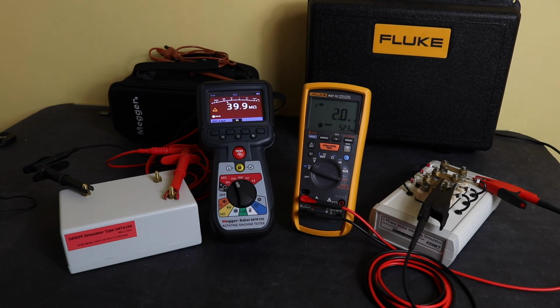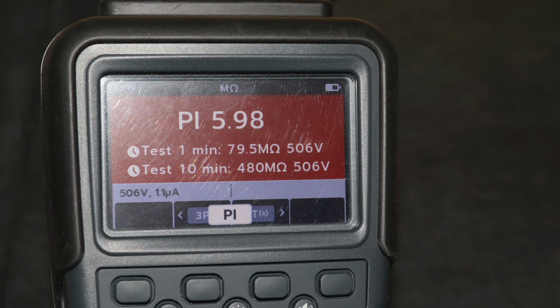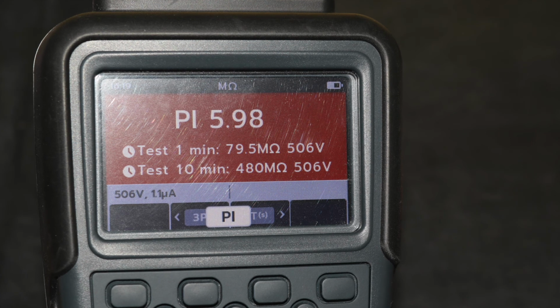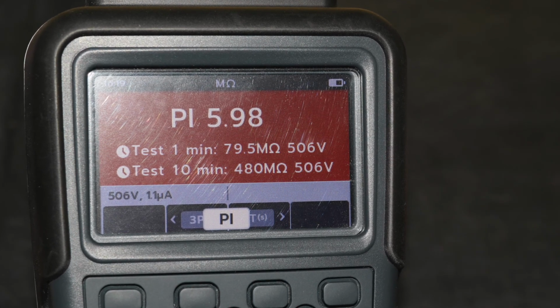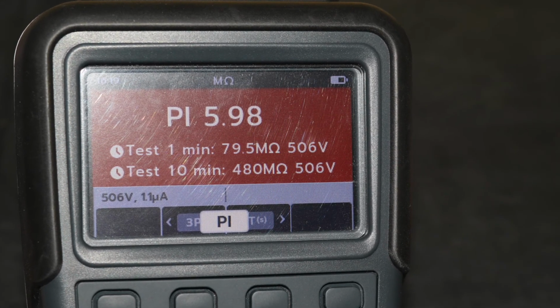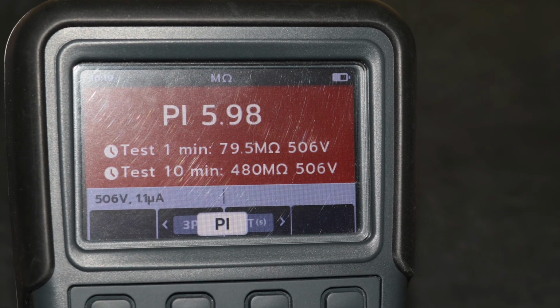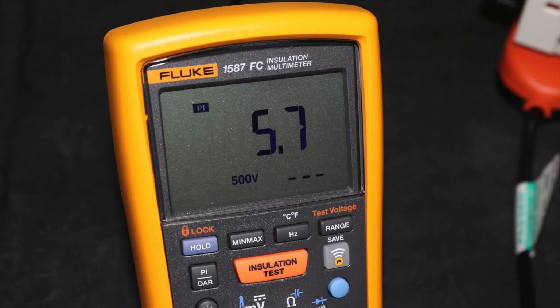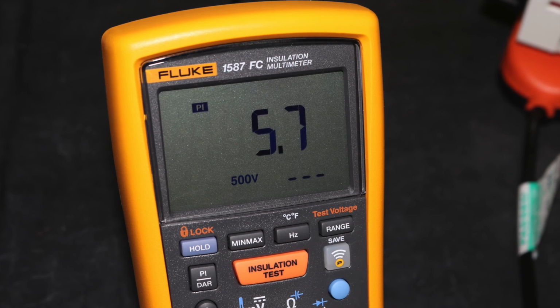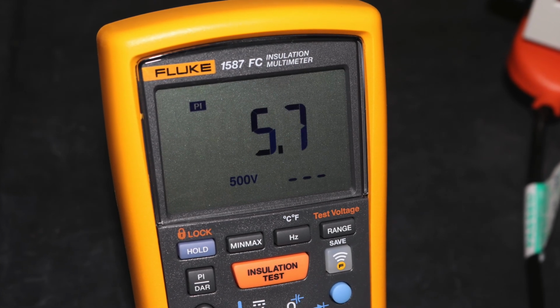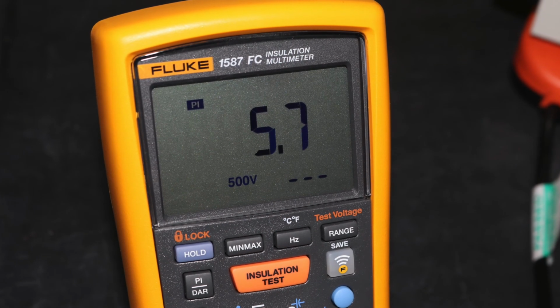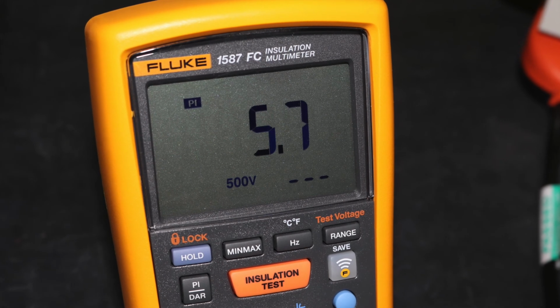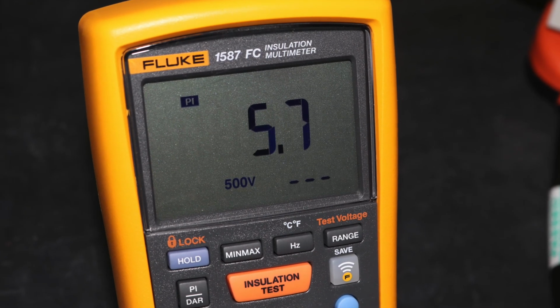Put a couple of screenshots up of the screens at the end of a test. With the MTR105, you get everything laid before you. You get the 1 and the 10 minute readings along with the PI ratio. With Fluke, it just resolves back to the actual ratio. You don't get the insulation values. There's no way of paging through them. You have to write them down as you're going along if you're not using the meter with an iPad to record the data.